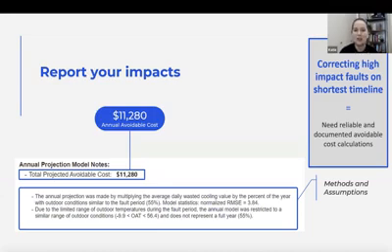And that's why I think it's important. It's a colleague, right? So you have people on your campus that are very smart. Most likely you have somebody who works in energy management that will question these results and be able to make some smart decisions on truly what you should be reporting, especially if you're talking about annual avoidable costs. There are some things that truly, I believe, would have happened forever. But this one in particular, I think you would have found a valve that was stuck closed when you changed seasons. So I'm glad you asked that question. Thank you.